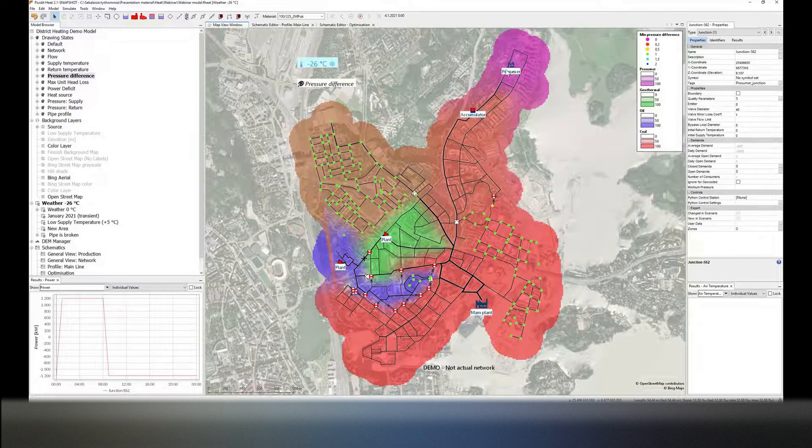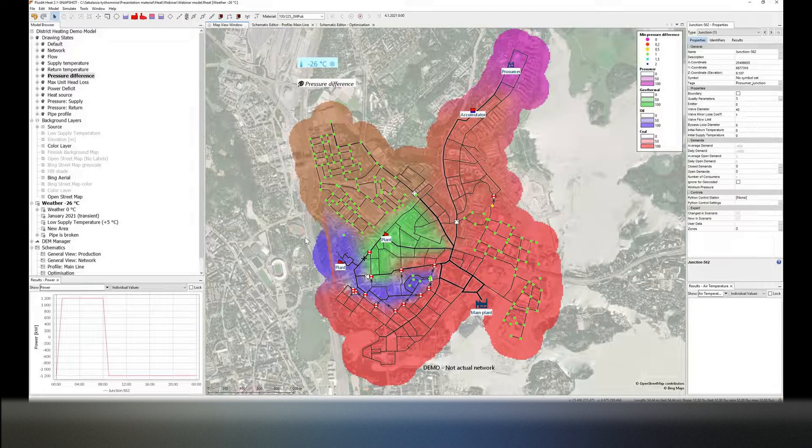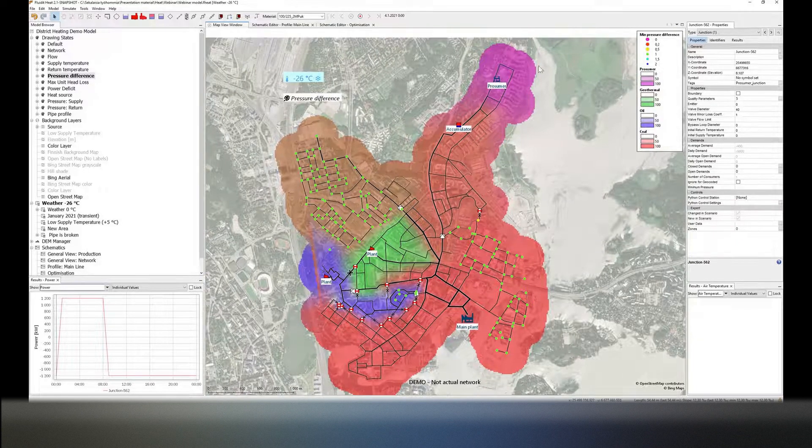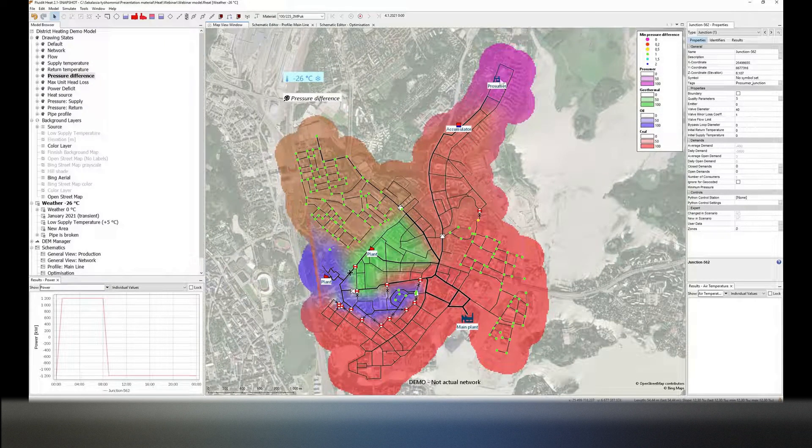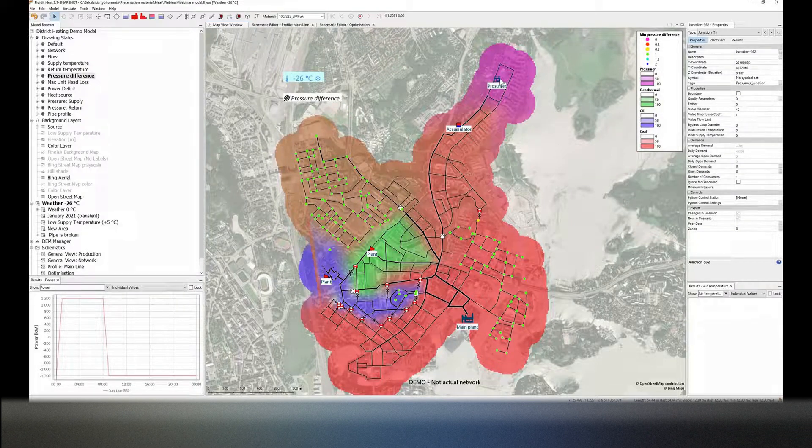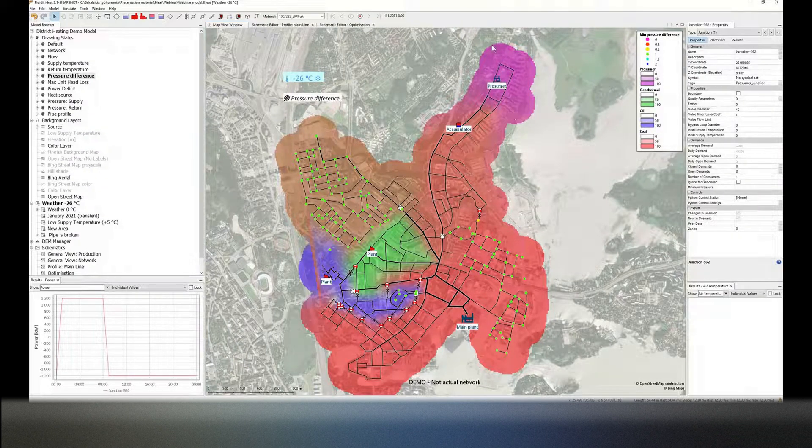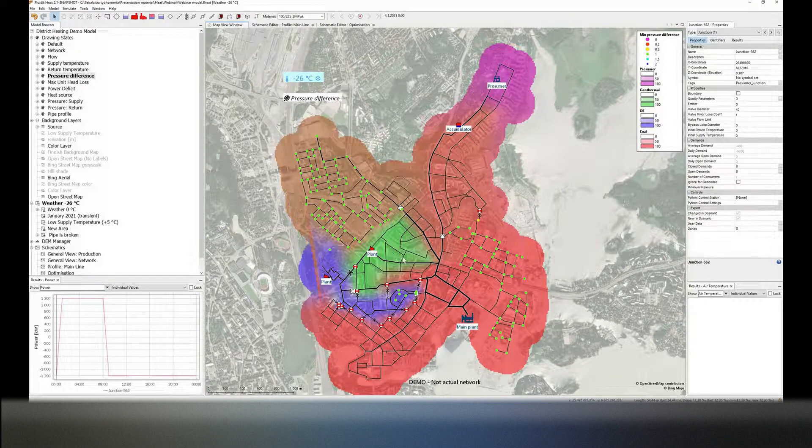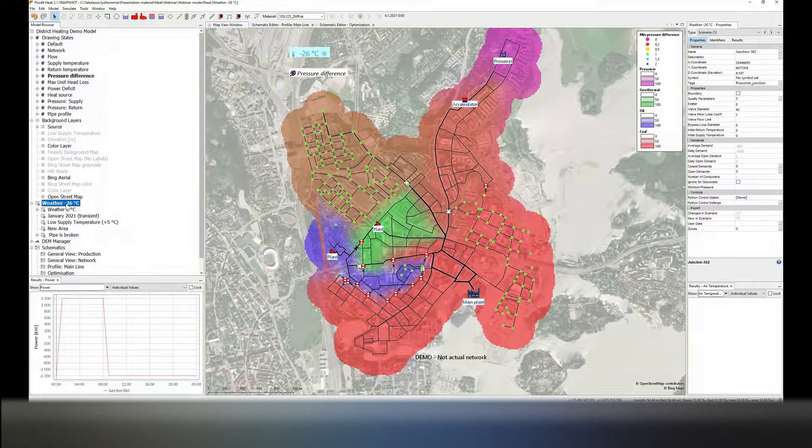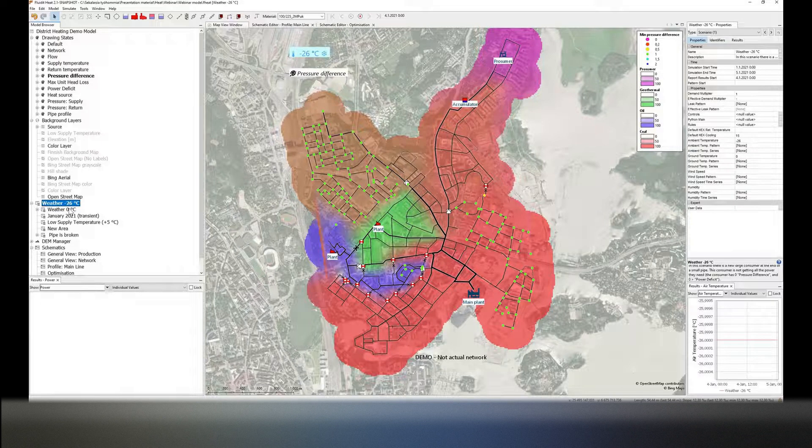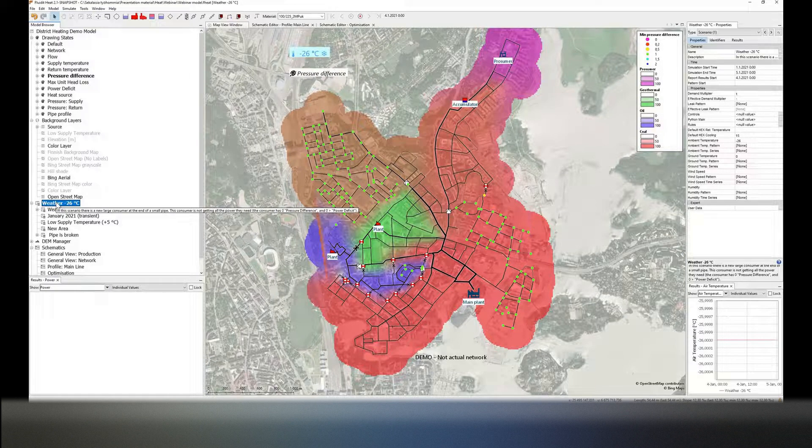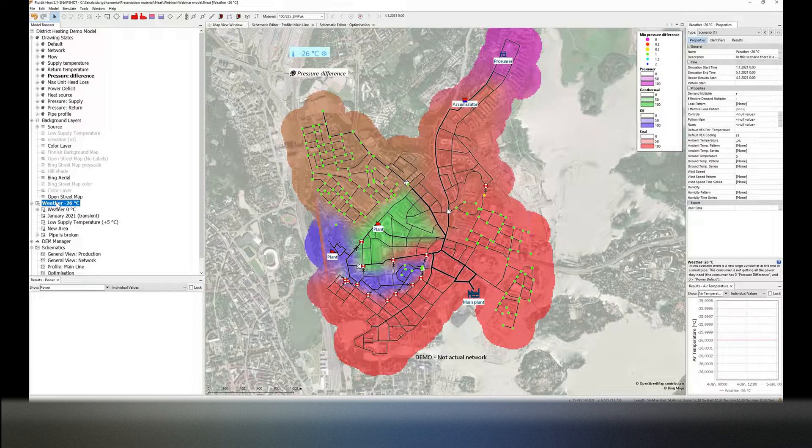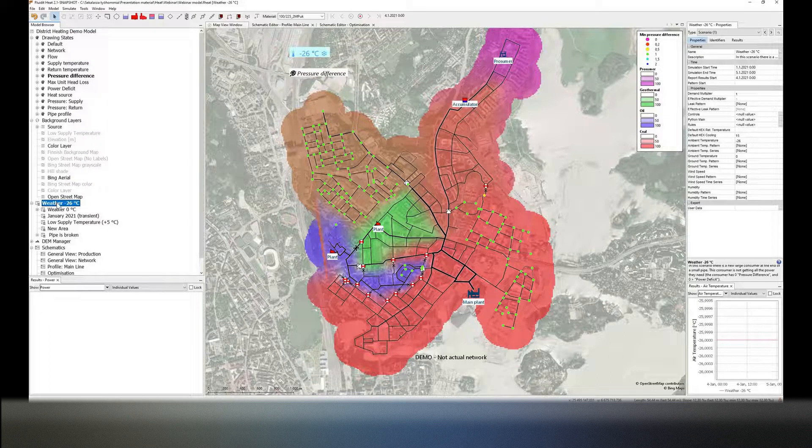We have now hypothetically thought that our main plant is a coal plant, this plant here is a geothermal plant, and we have an oil plant here. Then the prosumer is at the northern end. We are also showing the minimum pressure difference in the network, so if it drops down below a certain threshold value, obviously the heat exchangers are going to be having some problems taking the power. As can be seen here, the prosumer at those times when it is able to produce energy into the network is able to satisfy the rest of the consumers that are based in all of this northern part here. Then what comes, as I already mentioned, generally what we model is the date when we want to be really dimensioning the network.